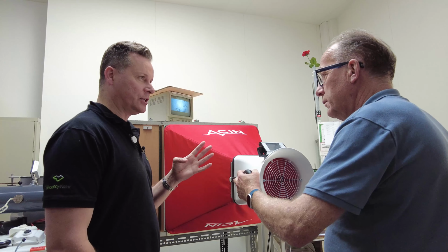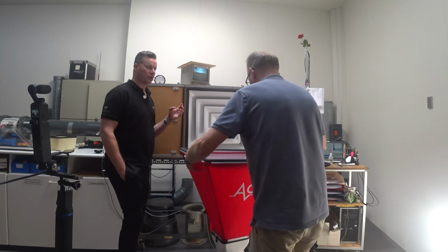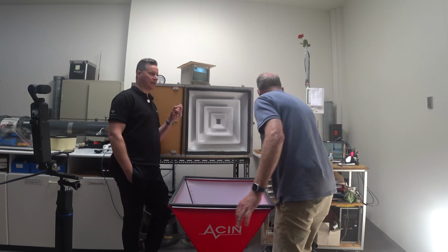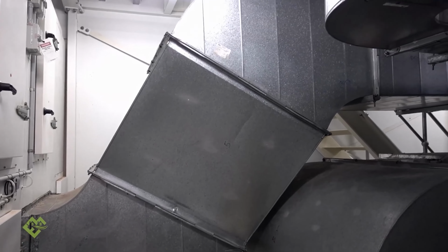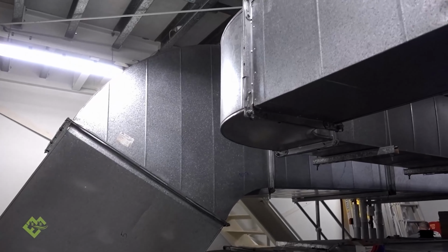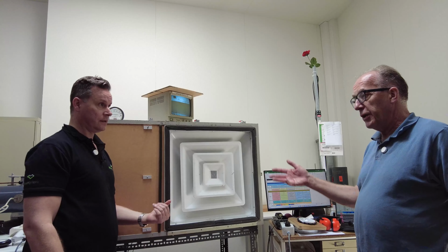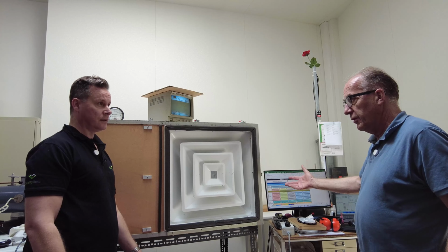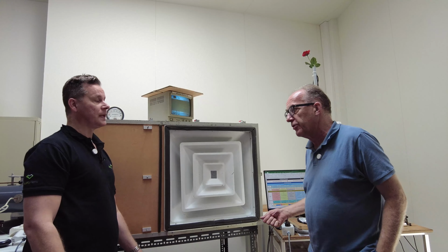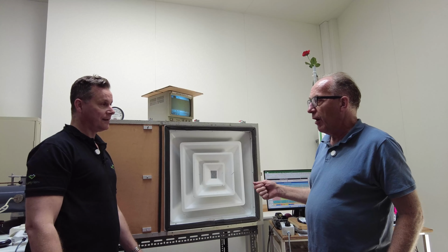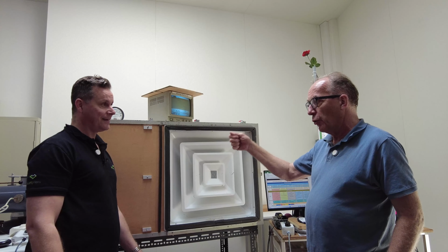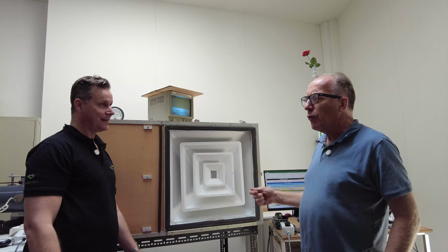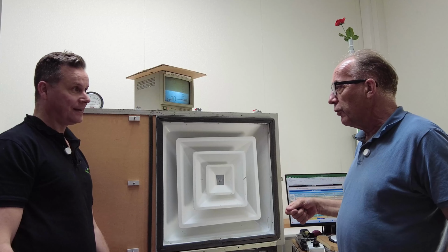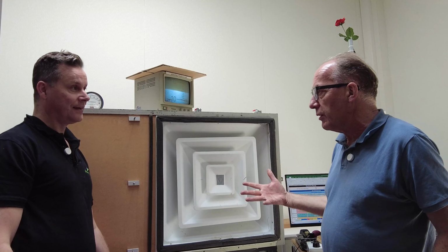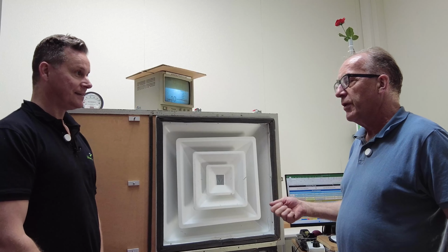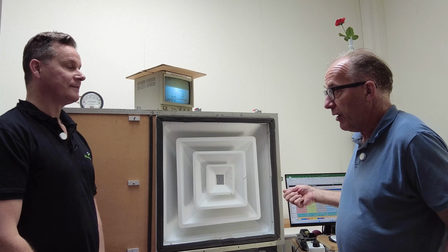Conventionally, how does this commissioning work in the commercial space when they're trying to line up the airflow from the air handler through to all of the outlets? What they normally do, they're not sure about the accuracy of their flow hood, or they know that it differs on different systems. They are all experienced commissioners, so they do a good job. Yeah. But they have a hard work because they first have to measure the total flow of the whole unit. Yes. They often do that with a pitot tube. You can already make easily 10, 15, 20% error with pitot tubes. Yes. If you don't do it properly, and not everybody is educated to do it.